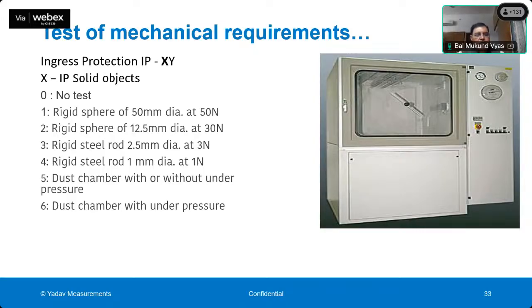So the first digit of IP51, which is 5, specifies the protection class of the meter against dust. The other numeral, in 5 and 1, the 1, specifies the protection level from rain. You can see 1, 2, 3, 4, 5, 6 specify the various levels of protection from dust or solid objects. The meter is specified to be tested as per the 5th level of dust protection. The meter is put inside a dust chamber and dust is circulated in the chamber for 8 hours. After 8 hours, the meter is taken out and subjected to the insulation test, and it is opened to see if there is any ingress of dust inside. So in short, the meter should be dust proof.